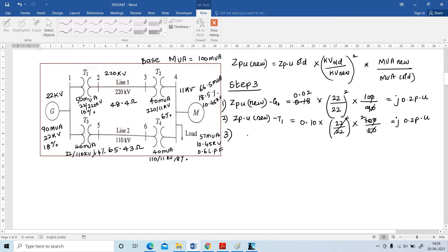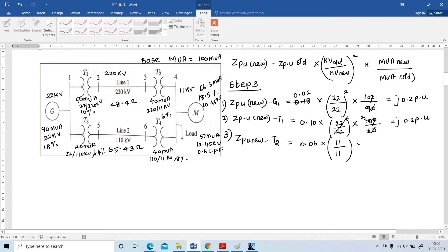Next, find ZPU for transformer T2. ZPU(new) = 0.06 × (11/11)² × (100/40) = j 0.15 per unit.